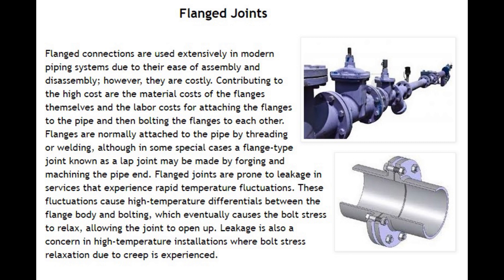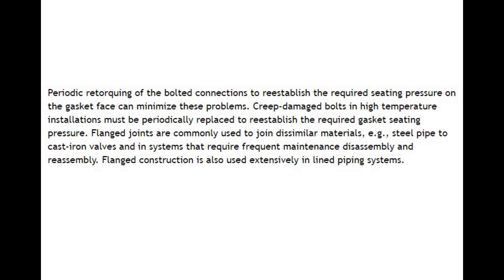Flanged joints are prone to leakage in services that experience rapid temperature fluctuations. These fluctuations cause high temperature differentials between the flange body and bolting, which eventually causes the bolt stress to relax, allowing the joint to open up. Leakage is also a concern in high temperature installations where bolt stress relaxation due to creep is experienced. Periodic retorquing of the bolted connections to reestablish the required seating pressure on the gasket face can minimize these problems. Creep damaged bolts in high temperature installations must be periodically replaced to reestablish the required gasket seating pressure.